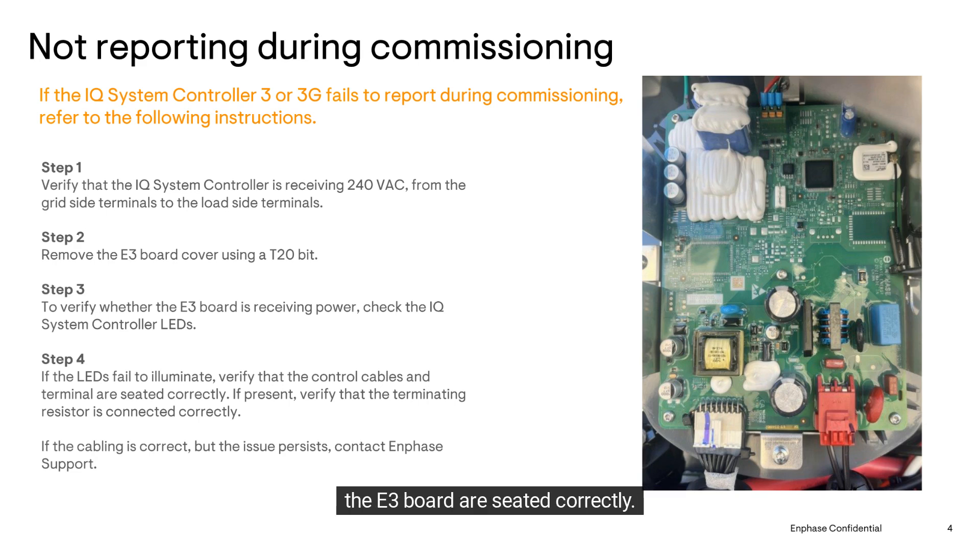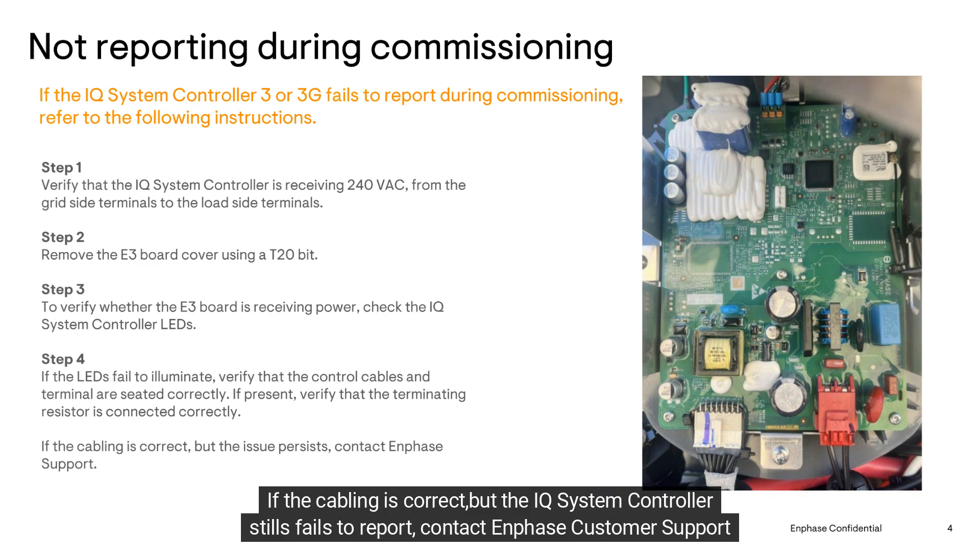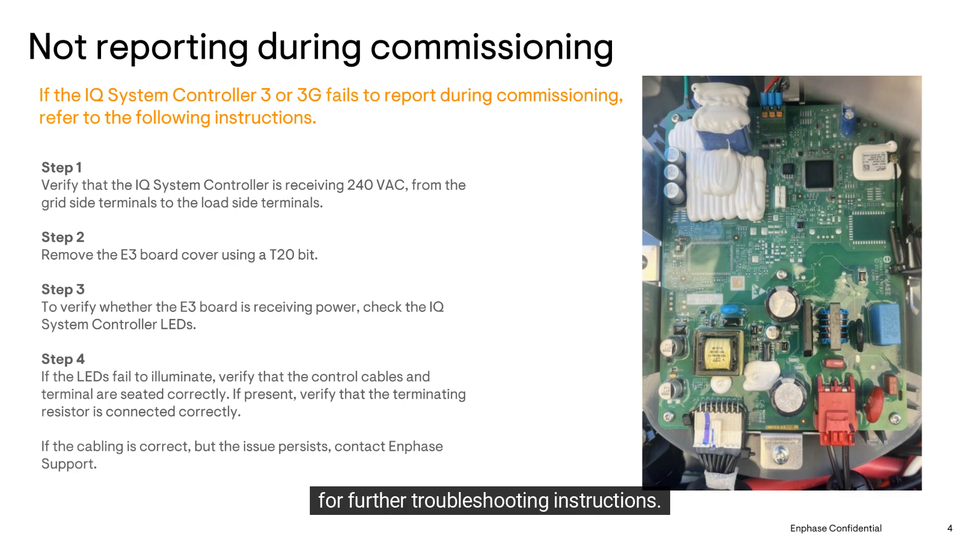If the LEDs don't illuminate, make sure that the control cables and terminals at the bottom of the E3 board are seated correctly. If the cabling is correct but the IQ System Controller still fails to report, contact Enphase customer support for further troubleshooting instructions.